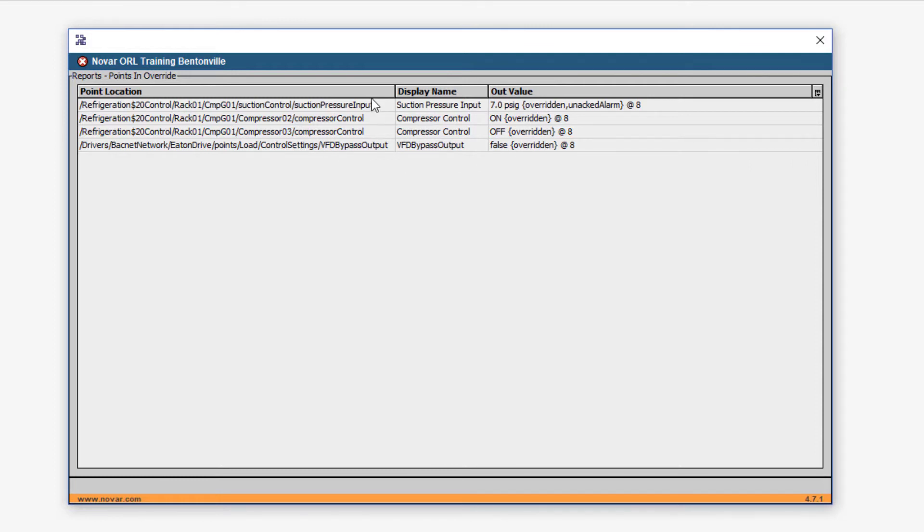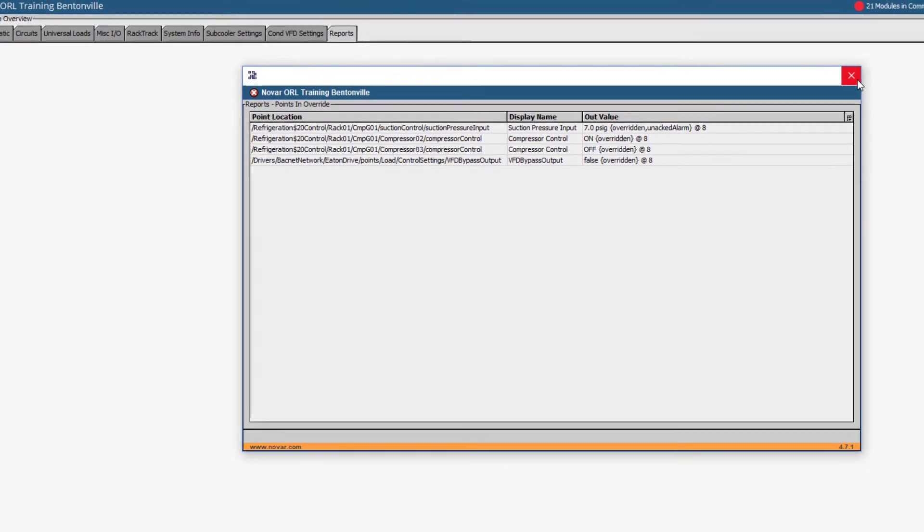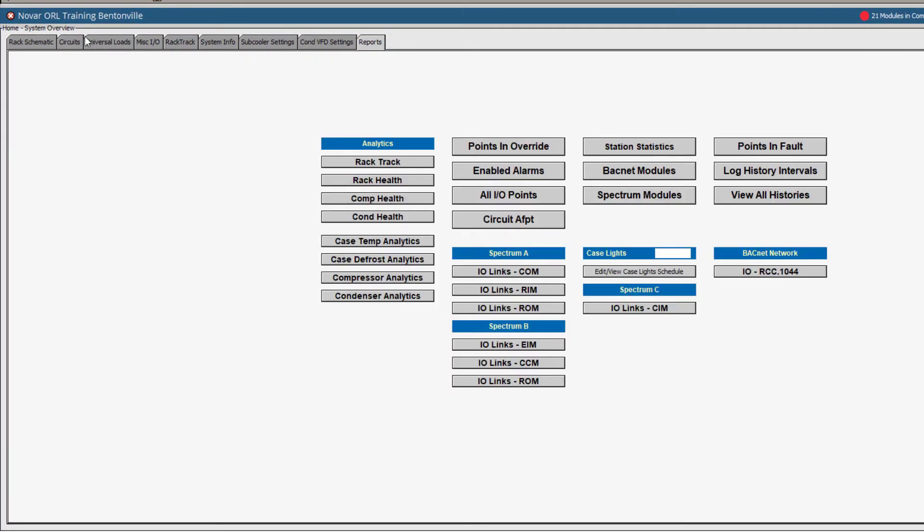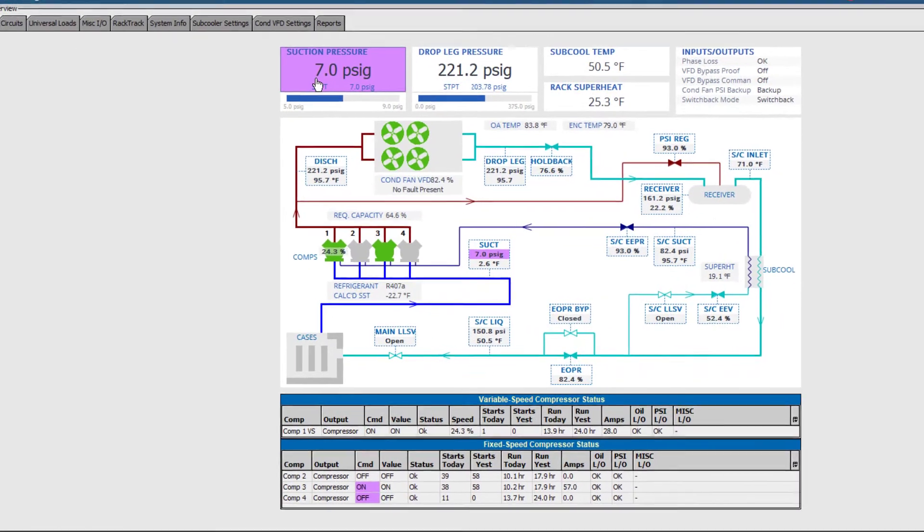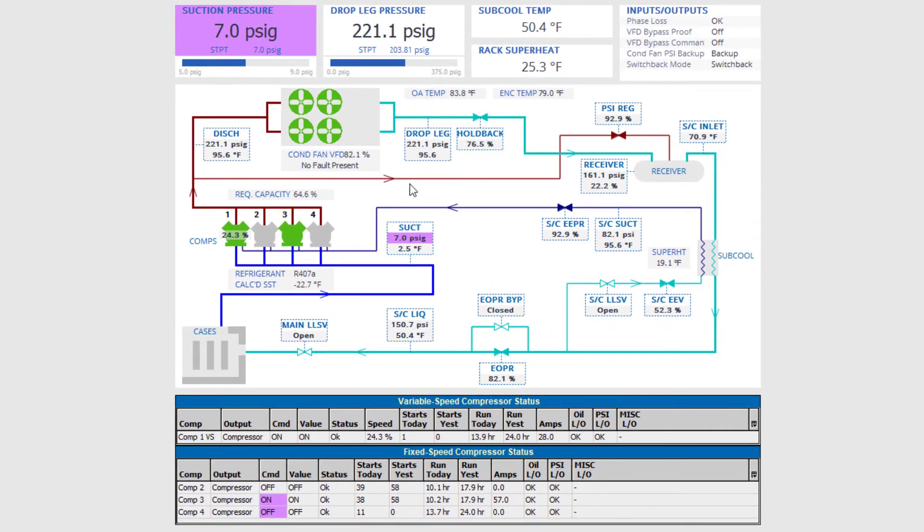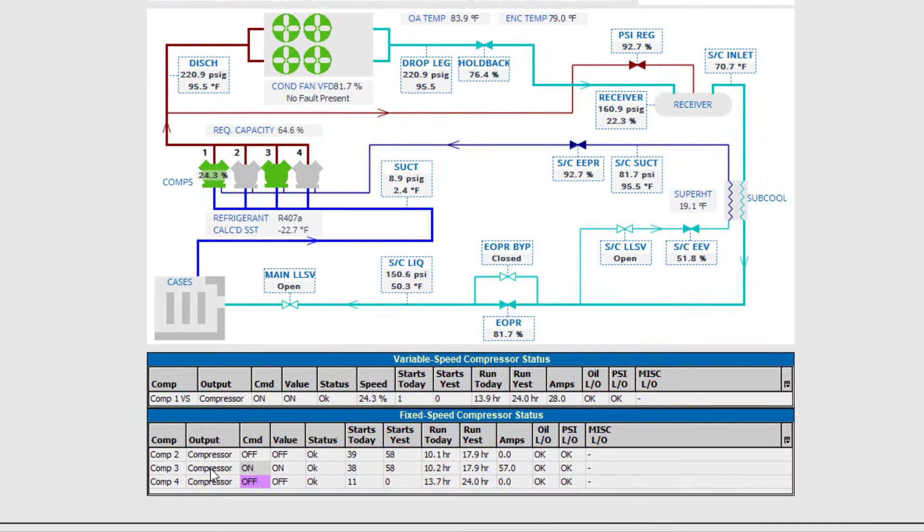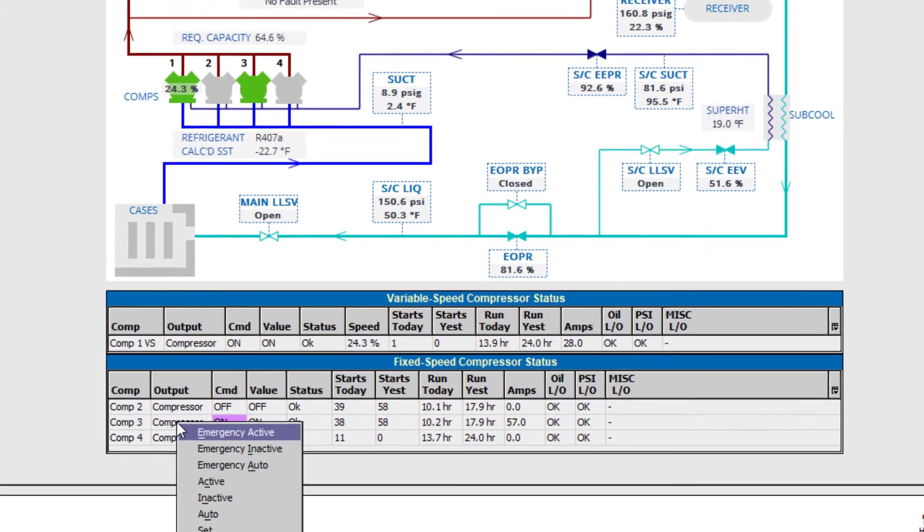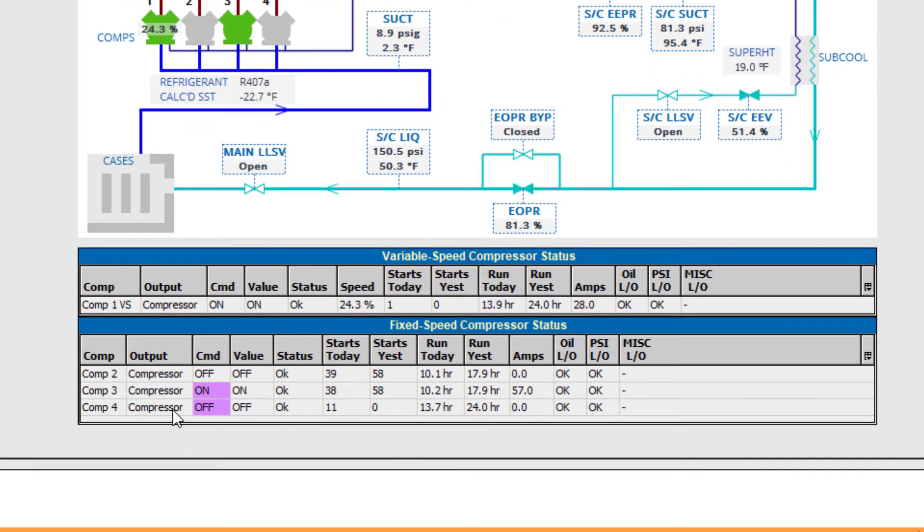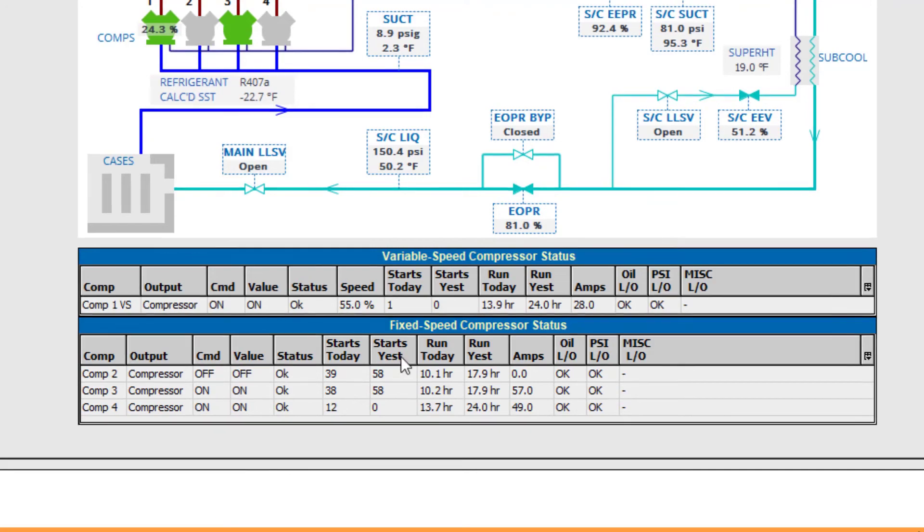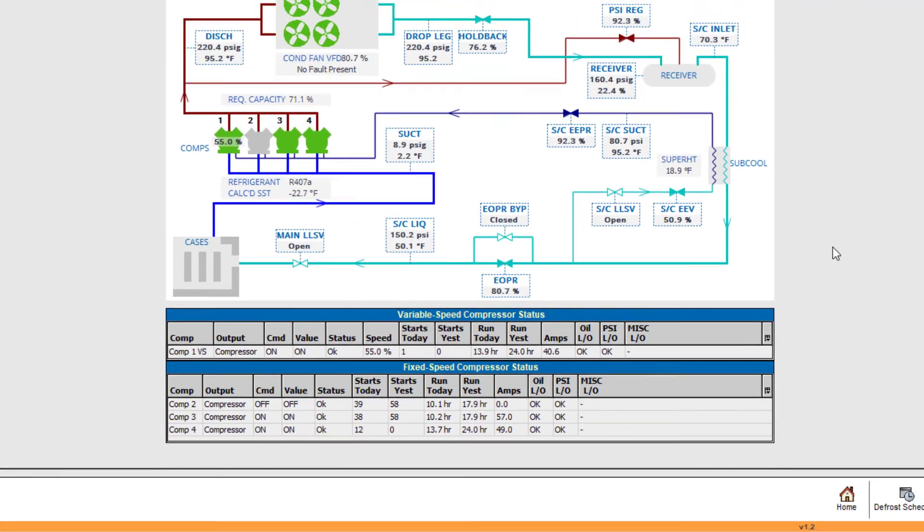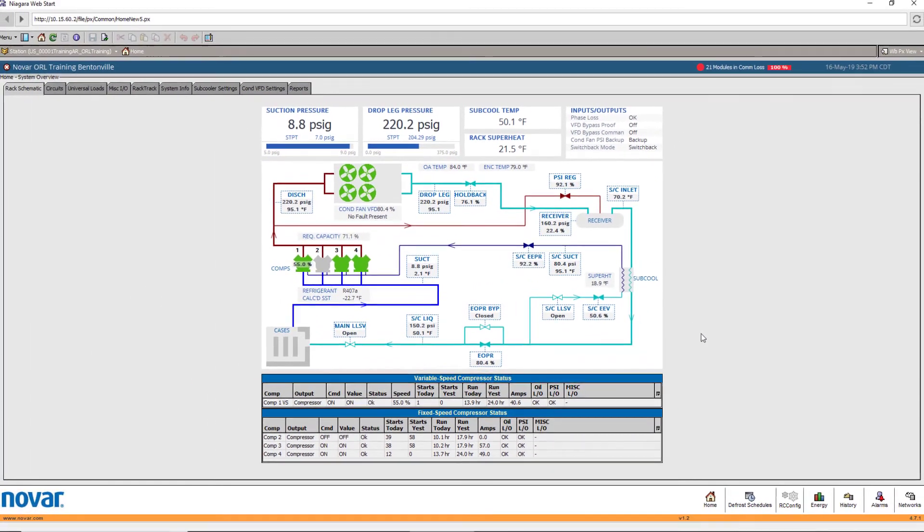Overrides that have been left active may be a workaround for a mechanical issue, and it is best practice to not remove any override you did not create yourself without first contacting the person who initially implemented them, or without having a technician on site to verify proper operation and control. This report should be checked to ensure that no overrides or emergency overrides that you are not intending to leave forced have been returned to automatic control prior to concluding your work.